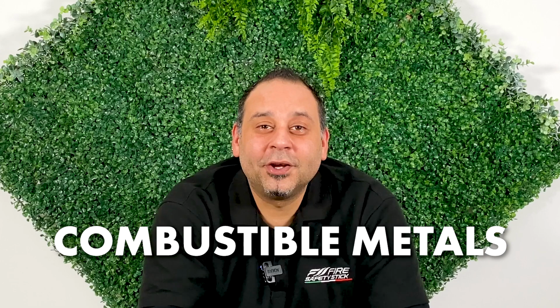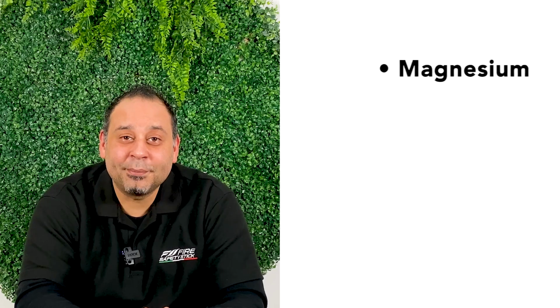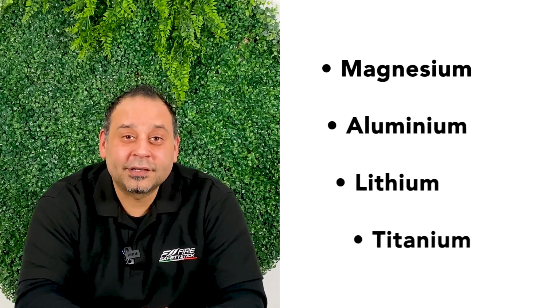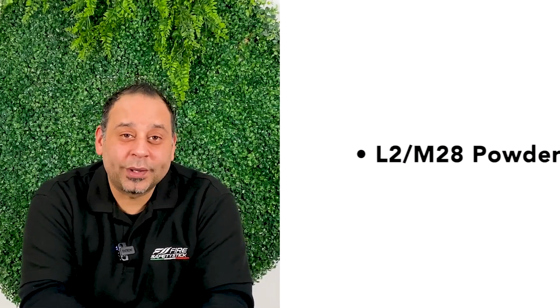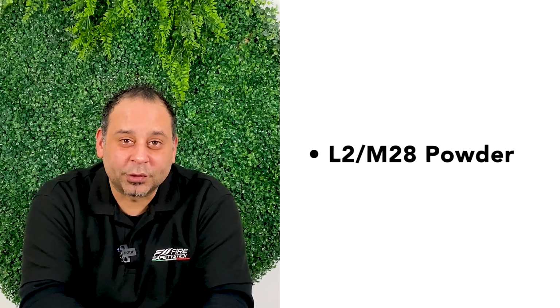Next on the list is combustible metals, also known as Class D fires. The fuel source used for this classification of fire can include magnesium, aluminium, lithium, titanium, and more. Although an uncommon fire, they require very high temperatures to ignite, and due to this are exceptionally dangerous and require specialist extinguishers. Extinguisher options include L2 or M28 specialist dry powder extinguishers, not to be confused with your everyday normal dry powder extinguishers.